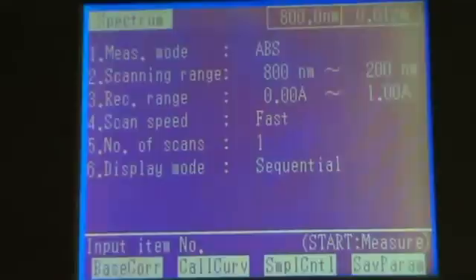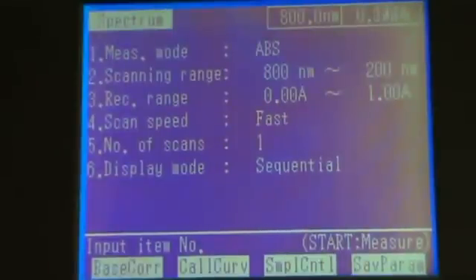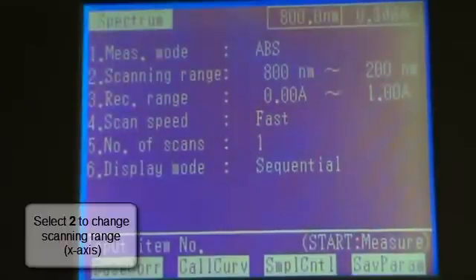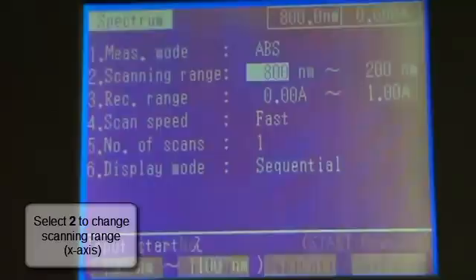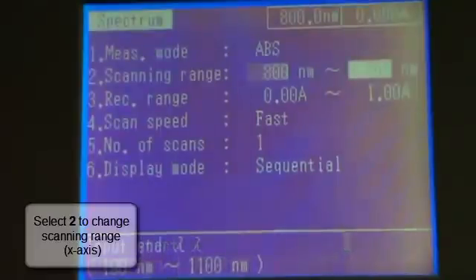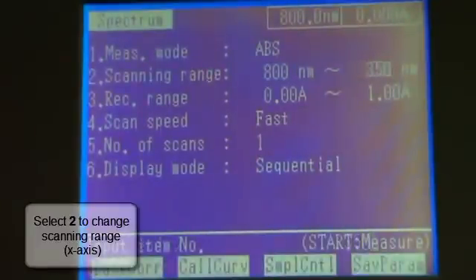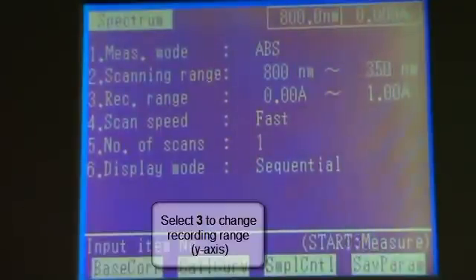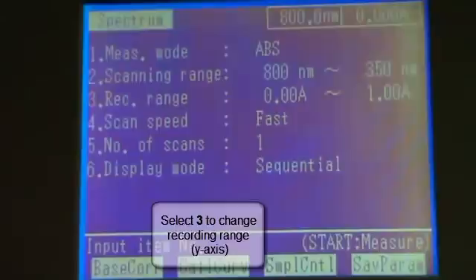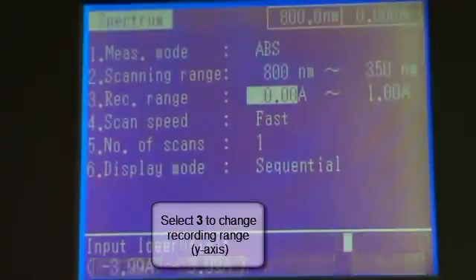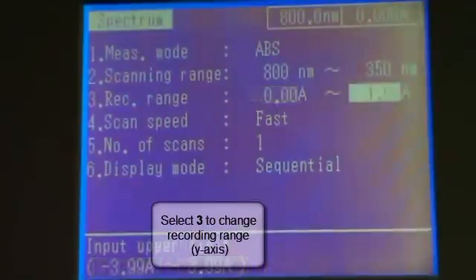We now need to enter a parameter for this experiment and again these should be recorded in your notebook. We are going to change the scanning range in this experiment so we select 2 to highlight the scanning range and enter in the wavelength range required using the keypad. Enter toggles from one end of the scale to the other.